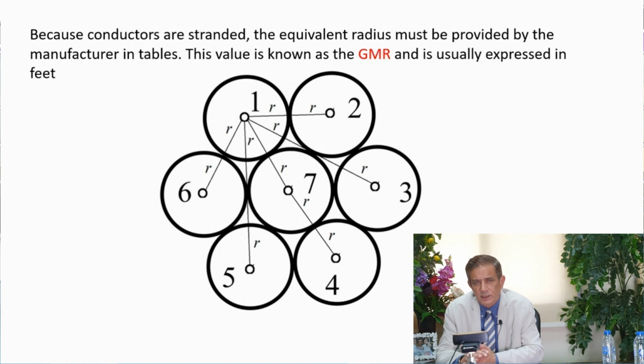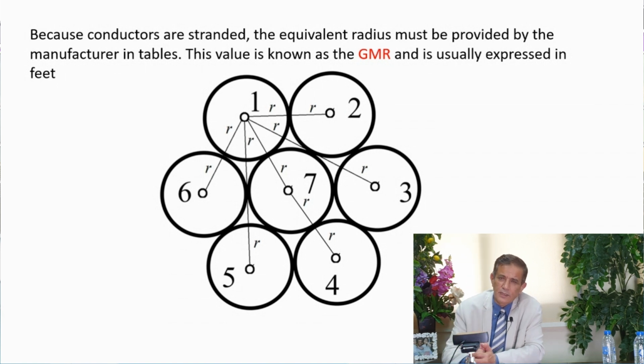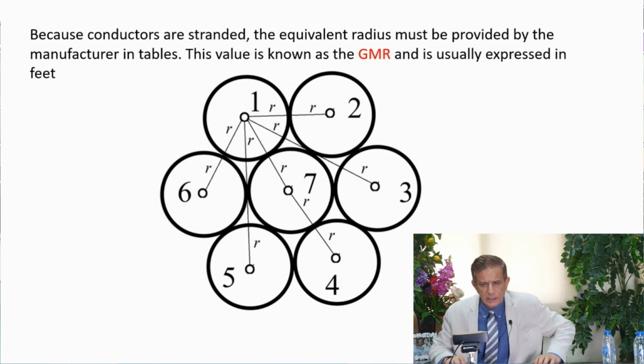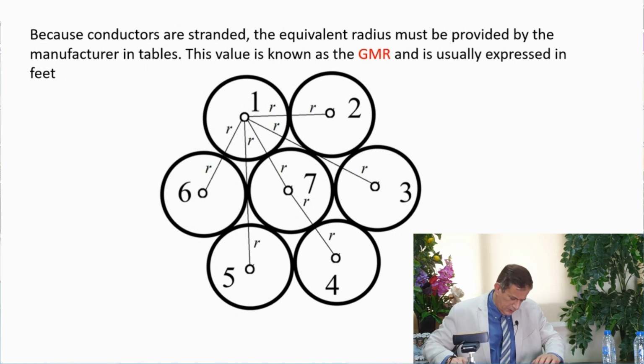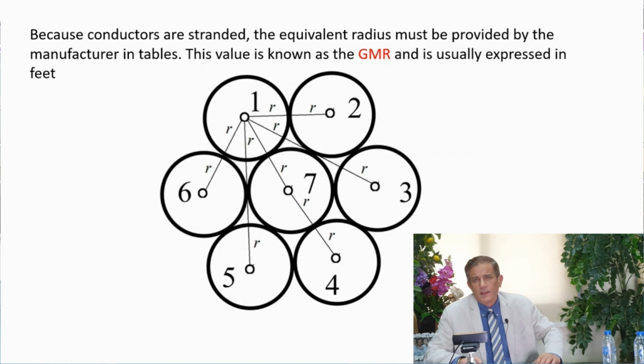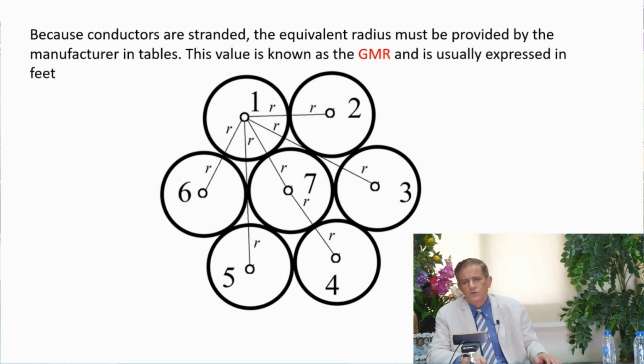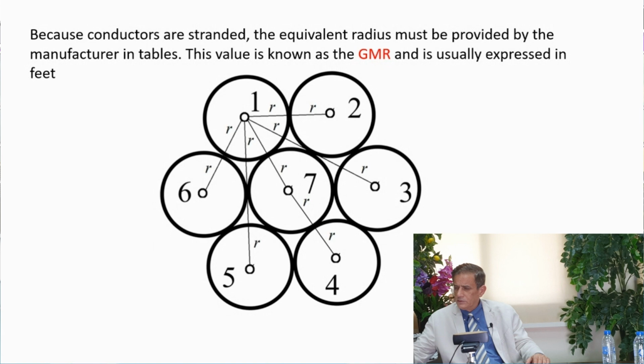I take the second conductor, multiply its self radius by the spacing from the other 7. I'll be multiplying 49 spacings and taking the power of 1 over 49 to get the geometrical mean radius, which is not practical. That's why the geometrical mean radius for such conductors is given in the manufacturer data sheet, as you will see. We can do it simply for 3-4 conductors, but for this it's difficult.